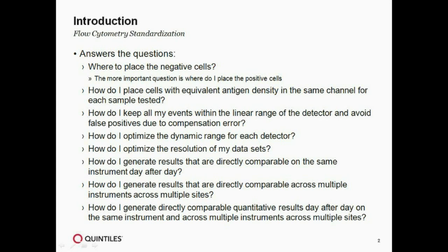All the time we were setting the negatives in our favorite place on our flow cytometers, we were asking the wrong question. The question we should have been asking is: where do we place the positive cells? Because the truth is, most antigens — especially things like CD4 — are very reproducible. And if your instruments are standardized, they should be in the same place every day.